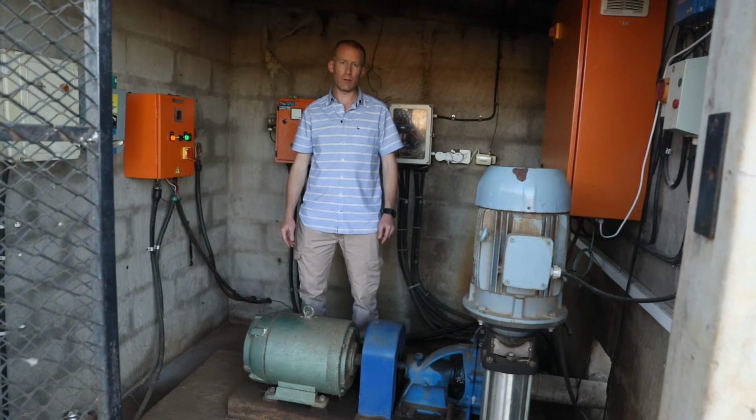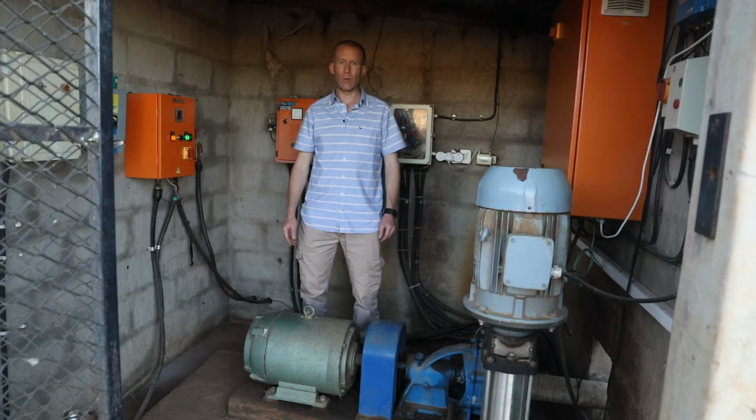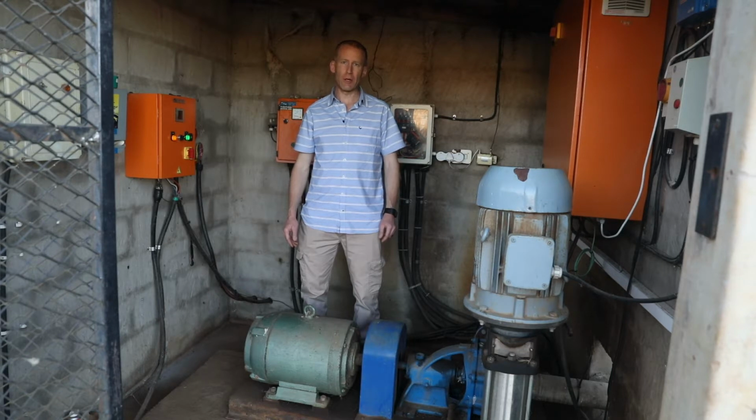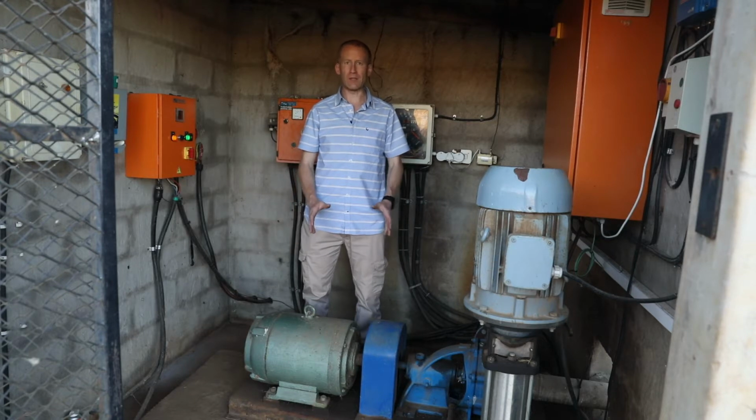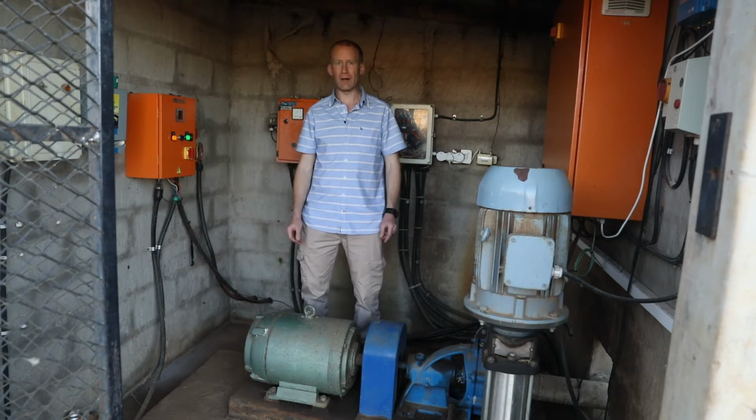This original pump and motor was also used to deliver water to Pivot number 1. When it was delivering water to Pivot 1, the actual power draw was 28 kilowatts. We performed a complete system optimization and determined that another pump and motor would be more suitable, and the location of the pump and motor could be optimized. So we've moved the pump and motor for Pivot 1 from this pump house to the Slurry Dam pump house. By moving the pump and motor to a different location and using a smaller pump and motor, we reduced the power consumption from the original 28 kilowatts down to 17 kilowatts.